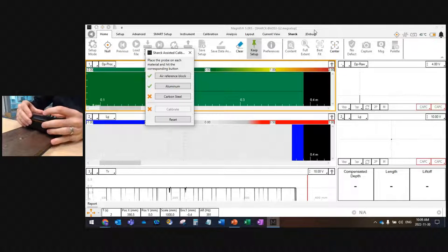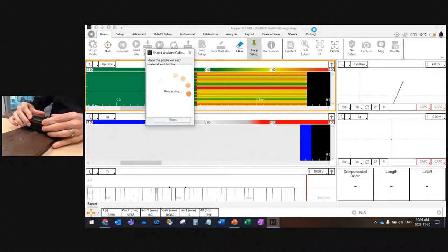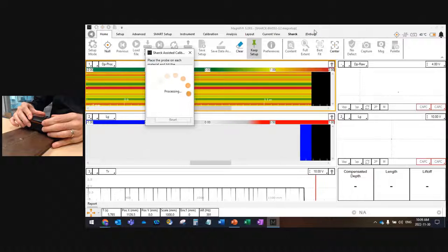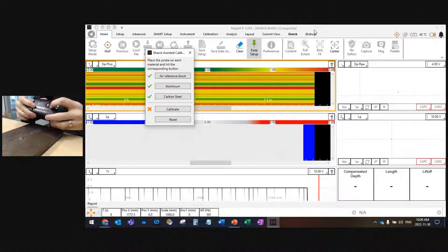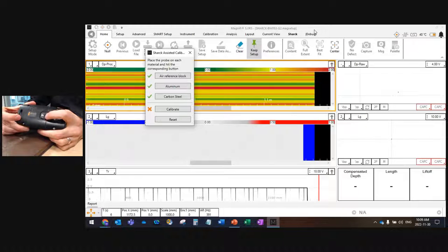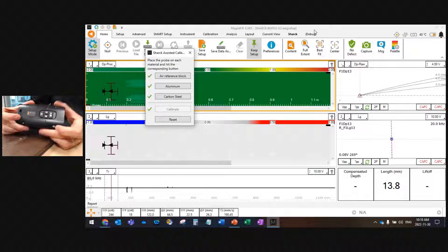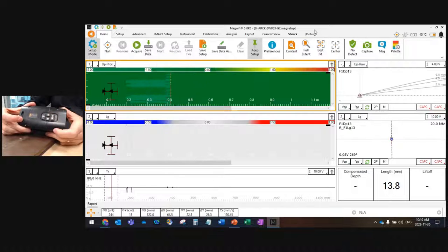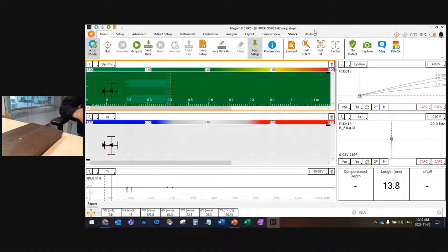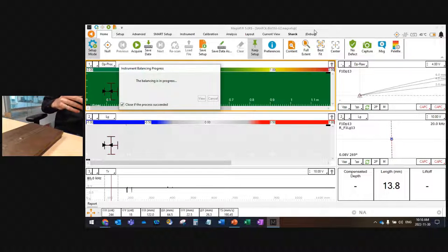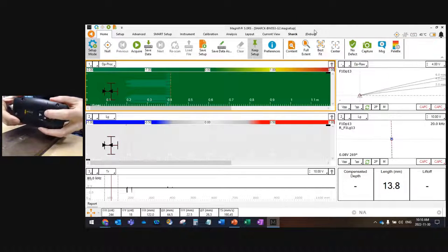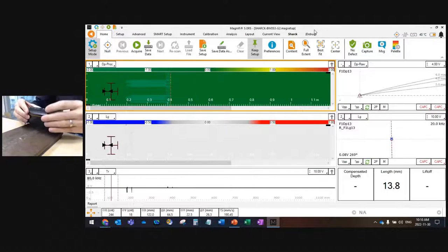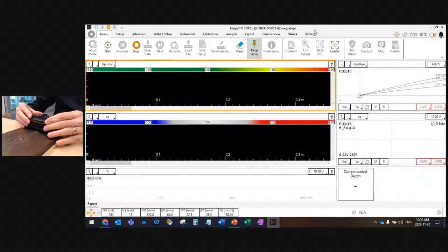Finally, I repeat the process on my carbon steel. This is just to give the software a reference of what type of carbon steel we are dealing with. You see all the color lines in the setup, it doesn't matter. It's not calibrated yet. So you need to press one last time to calibrate the probe. It took maybe two seconds, it's already done. Now my probe has been calibrated, my probe has been nulled. The only thing I have left to do is to do my actual scan. I null with my probe lying in the air, I press on it and I can start.